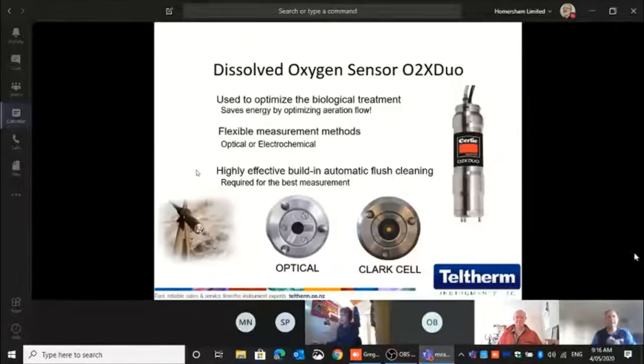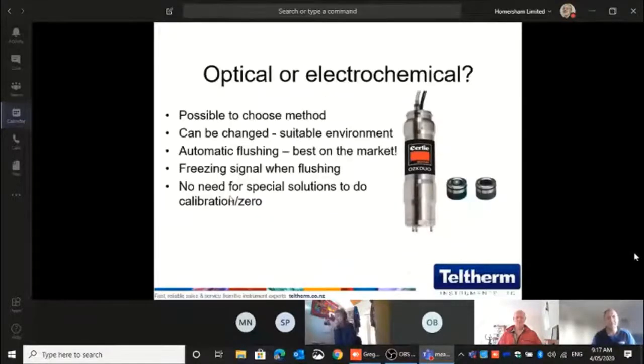The DO sensor, like I said, we have optical or Clark cell. We are not more accurate or better than anyone else. This is exactly the same technology. We use the same sensors. Where we know we are better is the cleaning. Like I said, from those 3 points, we spray up to 2 bar water or air directly onto the lenses. So cleaning is very effective.